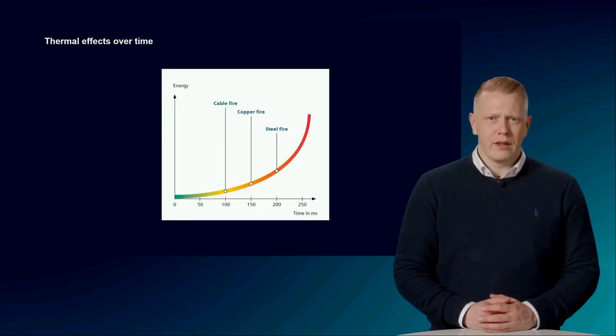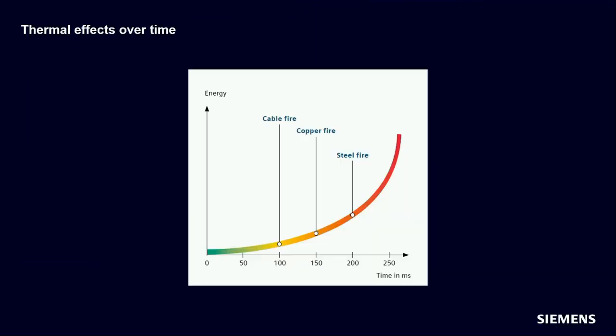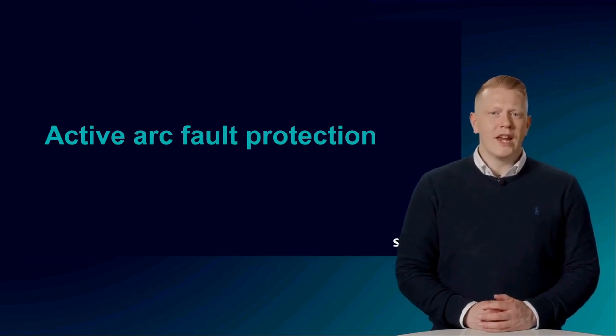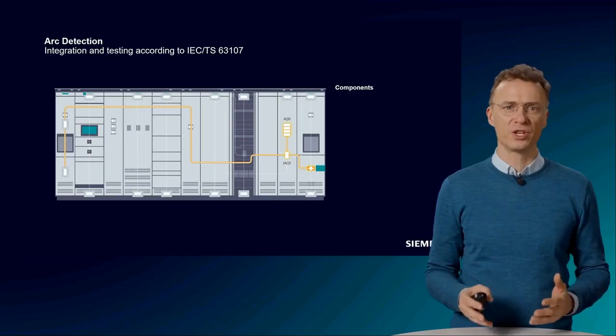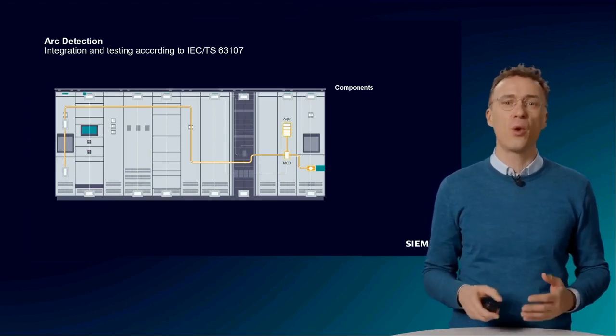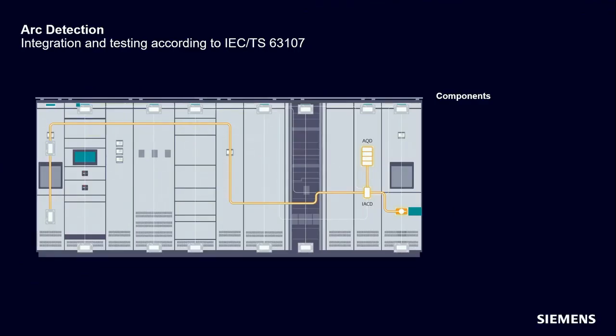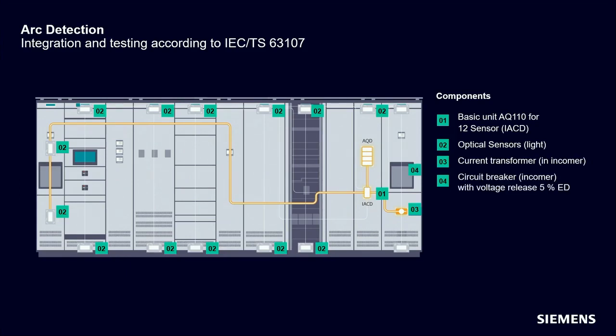Recalling the graph on thermal influence presented earlier, there is an increased risk of fire beginning in the range of temperature rise from approximately 100 milliseconds. Due to the exponential increase, the risk of damage grows with every millisecond. We would like to introduce a way to further reduce the tripping time and thus the energy released — an active arc fault protection through an internal arc fault mitigation system integrated according to IEC Technical Specification 63107.